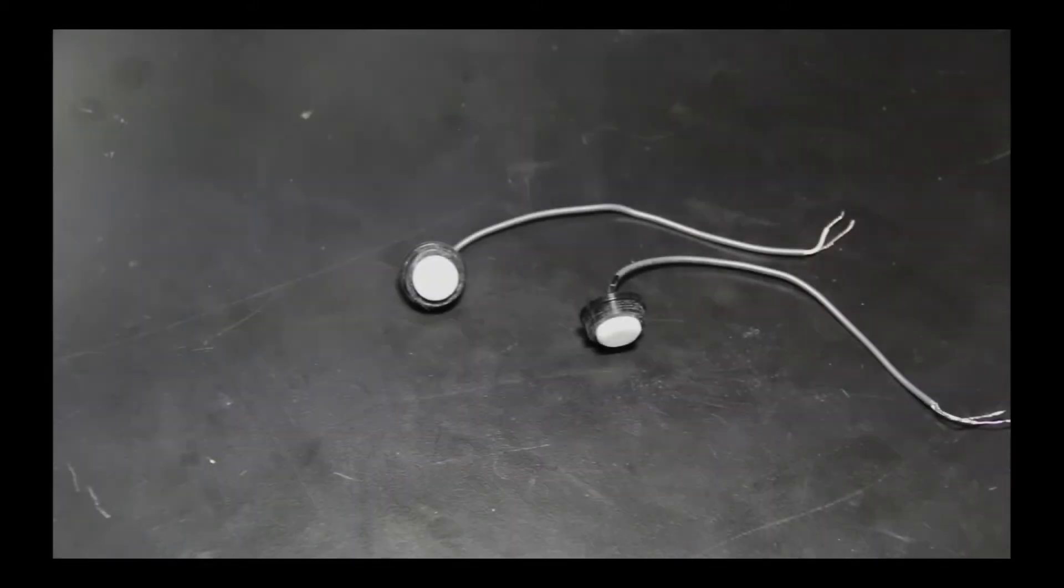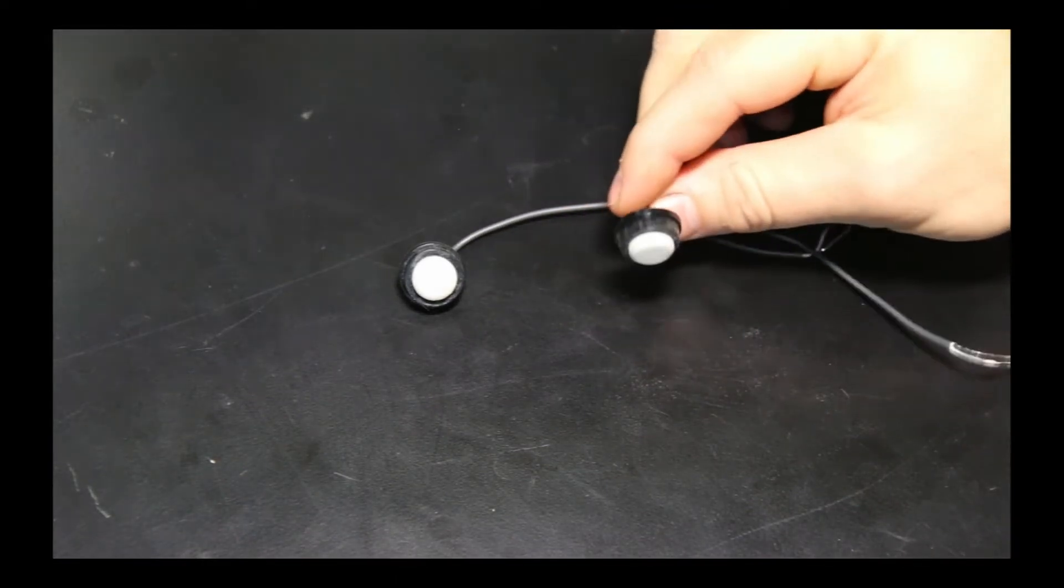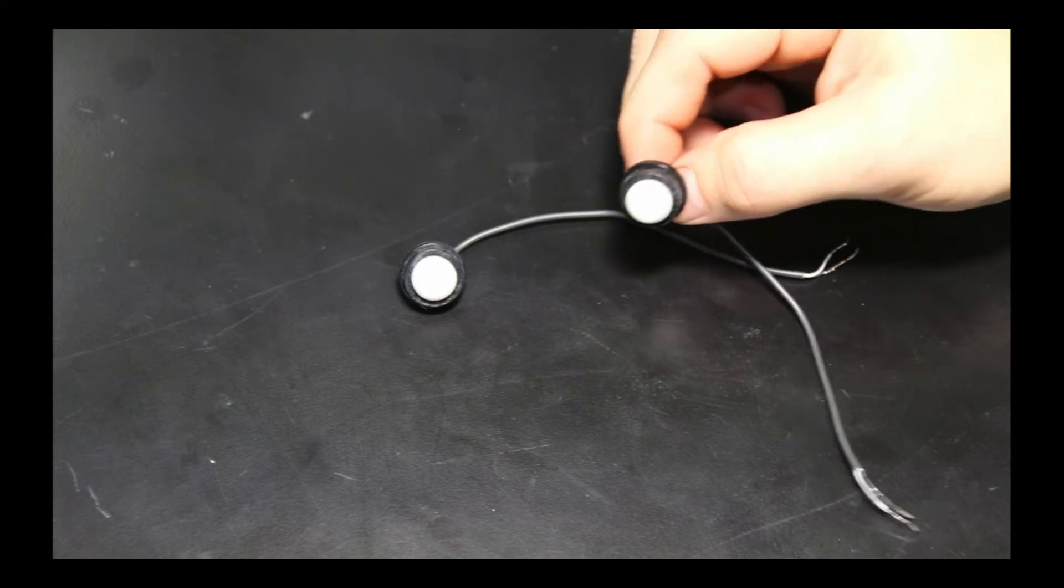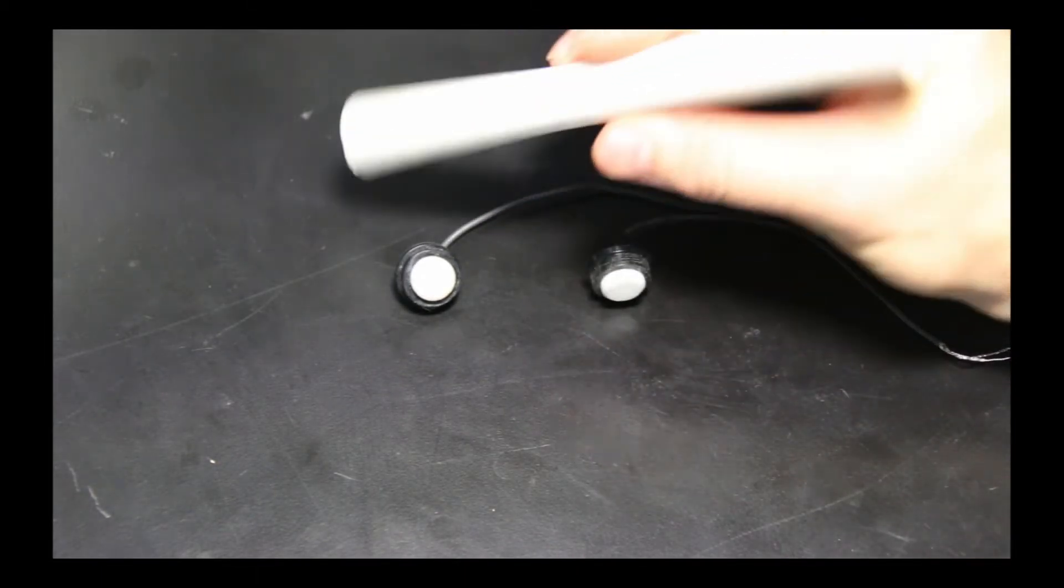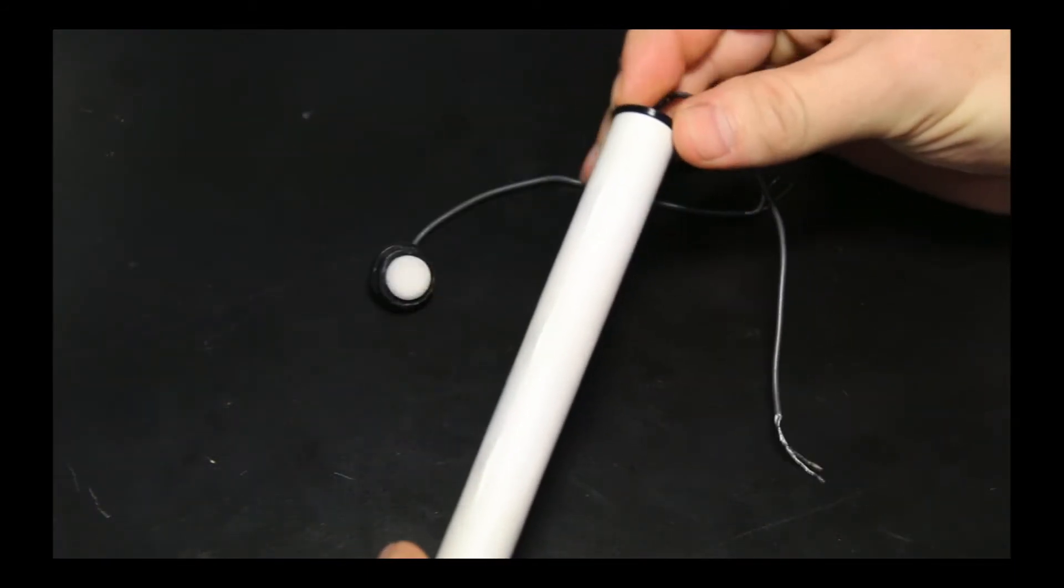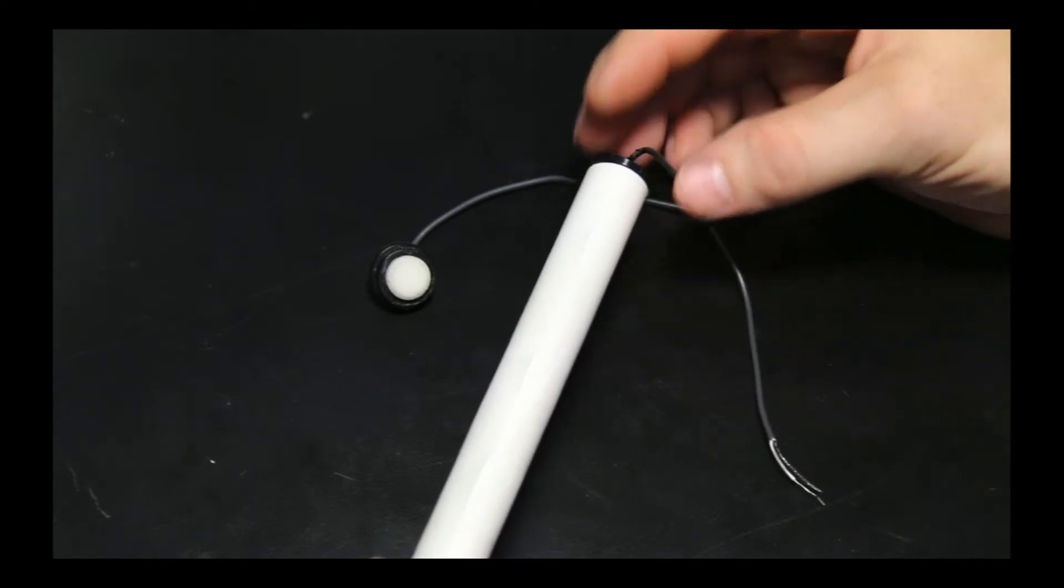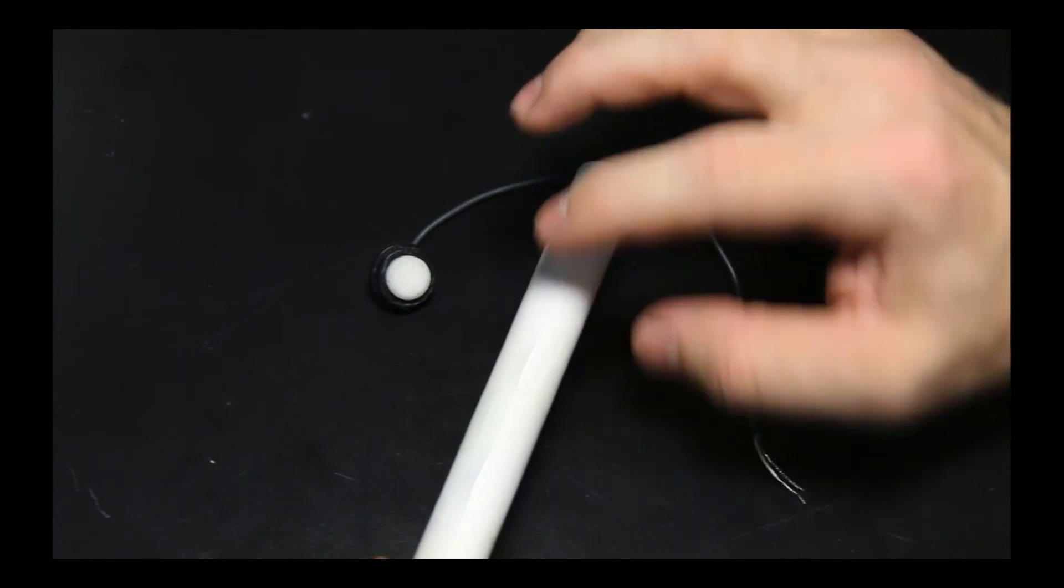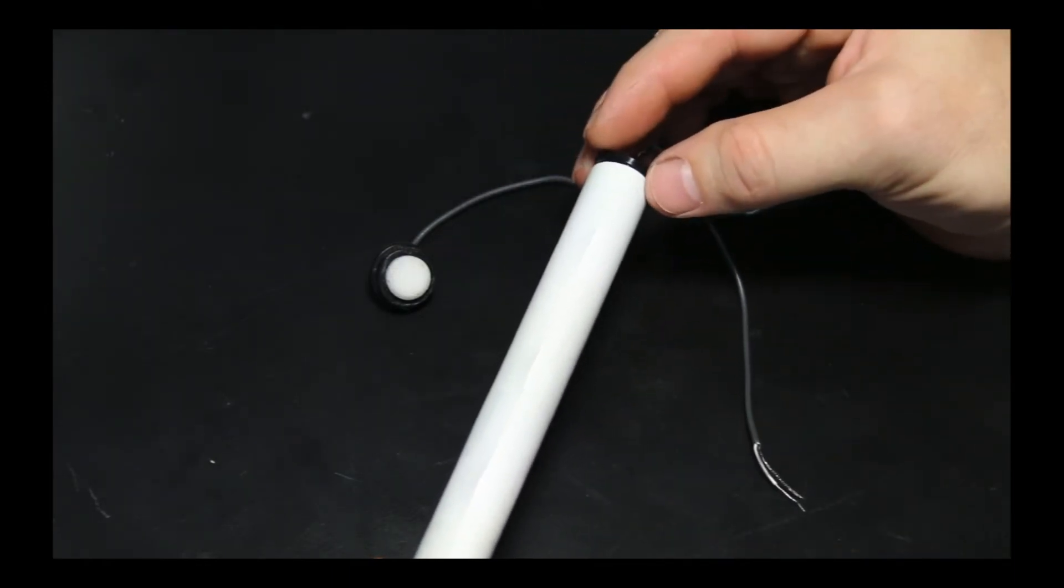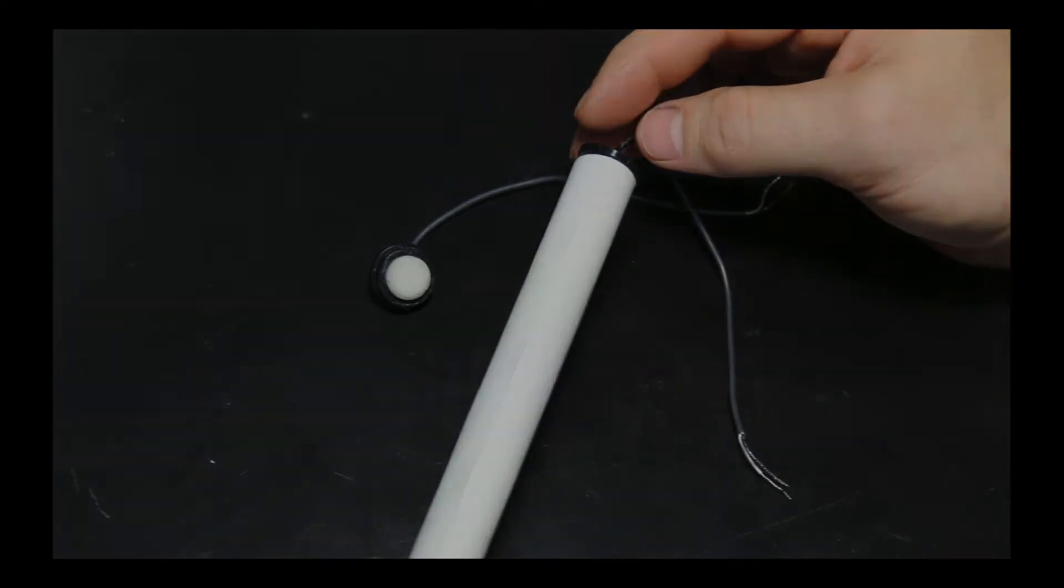These are the transducers I've been using for the demonstration. These are AudioWell 200 kilohertz air transducers. They market them as natural gas, but they'll work for any kind of gas. What I've done is created this tube out of paper and I insert each transducer into each end of the tube. That gives me a reference of a known distance between the sensors and zero airflow in the tube or near zero. This is a nice place to start when you're first bringing up the EV kit and becoming familiar with the chip and your transducers.